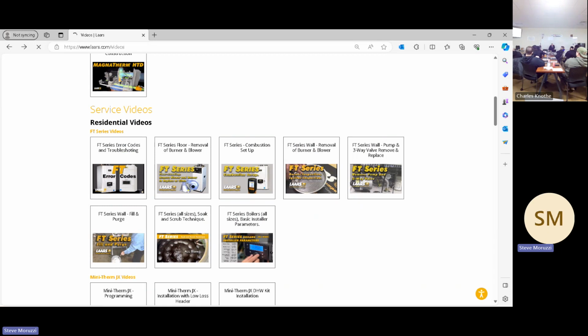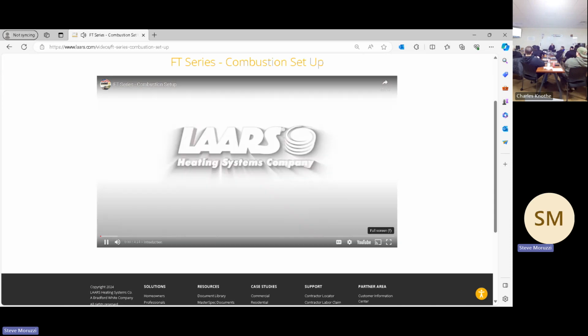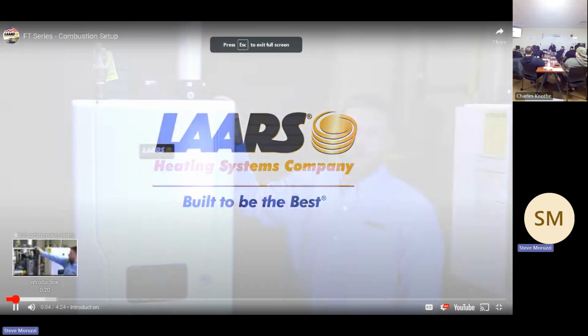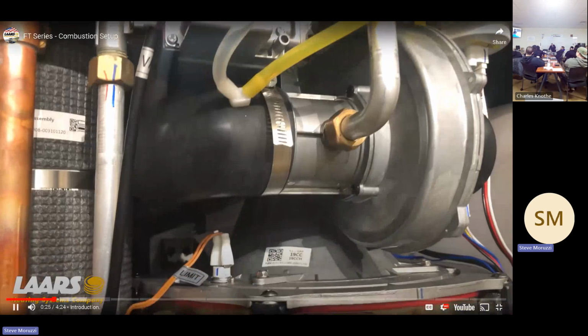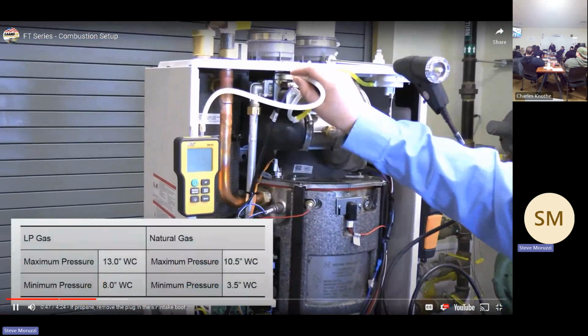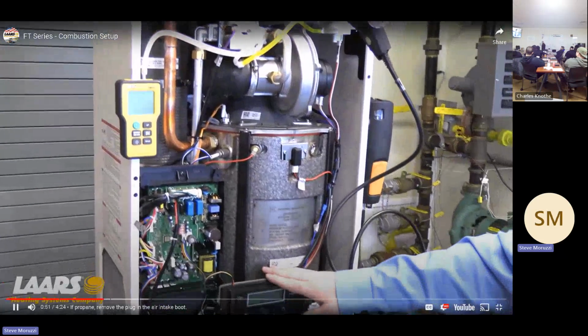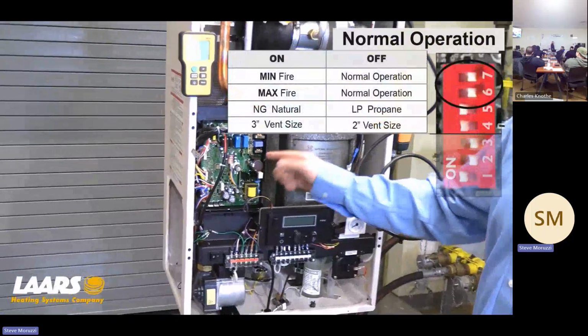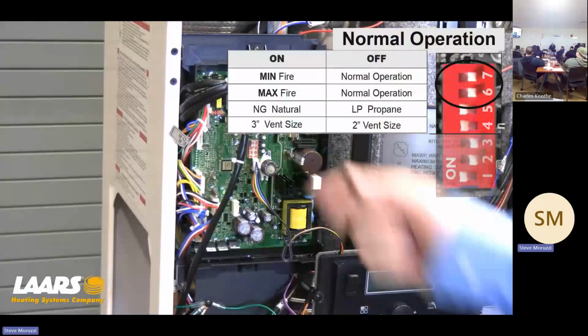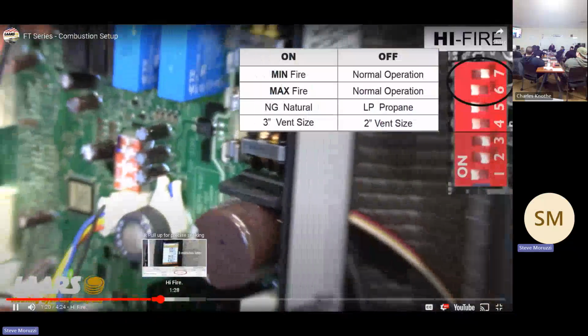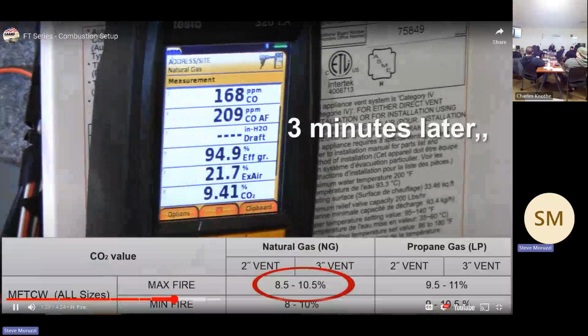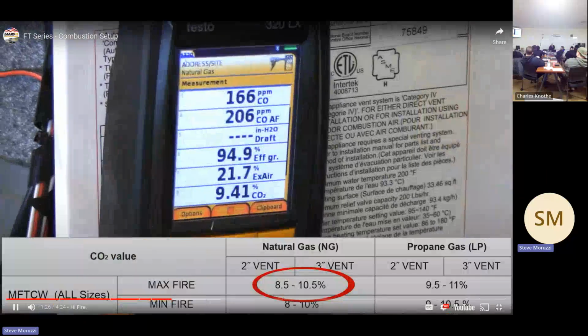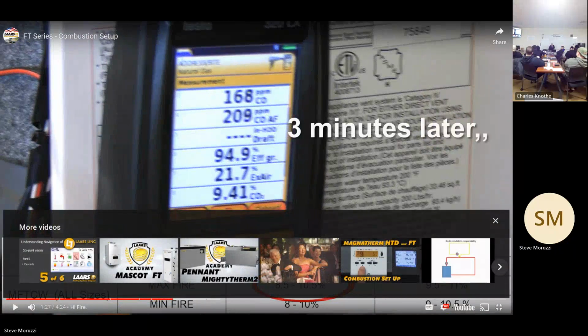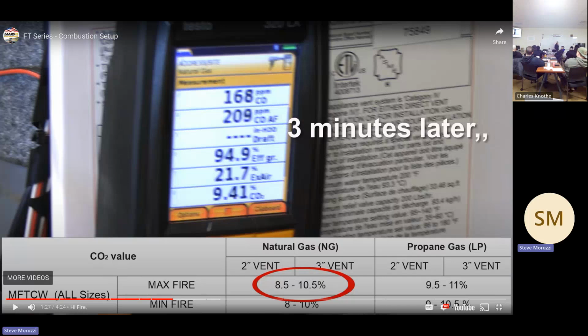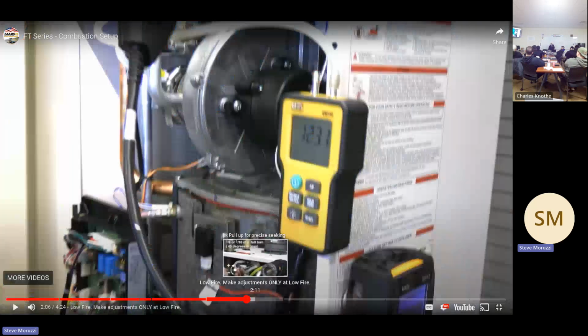How to do a combustion setup. Pull this up, and let me go to full screen. Here's an example. Again, there's audio to this, and how to remove the cover. Now, the combustion setup on this product is going to be the same as on the floor 199 models. It covers DIP switches 6 and 7, putting your analyzer in the flue, checking incoming gas pressure, and setting up combustion. We even give you the charts right at the bottom of the screen. Let me pause this and X this out. They show what your CO2 values should be at high fire and low fire. So everything is right here, showing you how to do this.